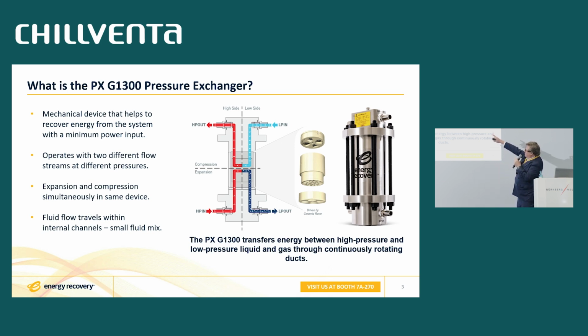And then you go from the bottom left to expansion, where the fluid has been expanded and returns to the liquid receiver. And if you go to the upper right, at the HP out, returns back to the gas cooler. So in effect, the PXG is lifting about 60 bar by using these two fluid flows. This cylinder is rotating at a speed between 250 and 1000 RPM. So the speed increases as the pressure increases. As the pressure increases, the exchange increases, and so does the total efficiency. So this is the most innovative device concerning COP improvement, amongst other benefits, in CO2.